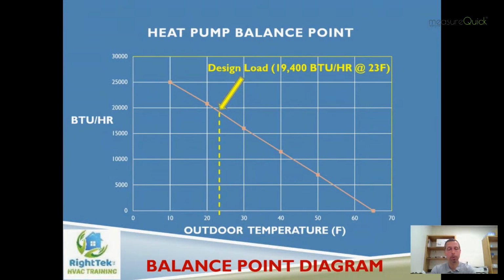That's probably a little bit beyond the scope of this conversation right now if you're not familiar with it. But we start there at 65 degrees, which is considered a point of 0 heat loss. I plot my design heat loss at 23 degrees, that's the 19.4, and I take a ruler and draw a straight edge. What that orange line represents here is the heat loss of the house. And you'll notice it's very linear. The colder it gets outside, the greater the rate of heat loss for the structure.